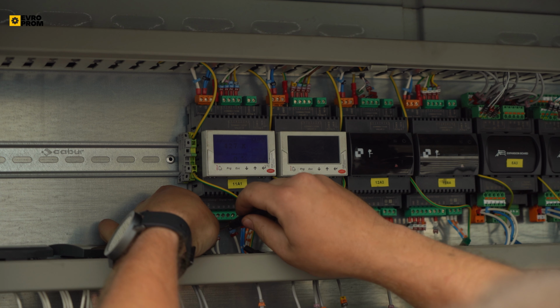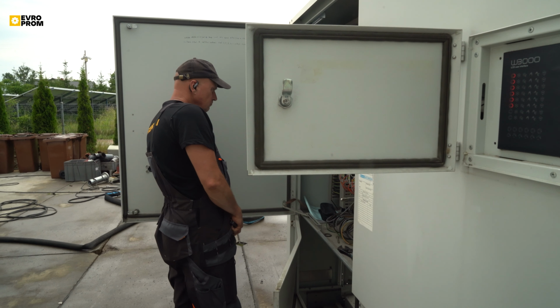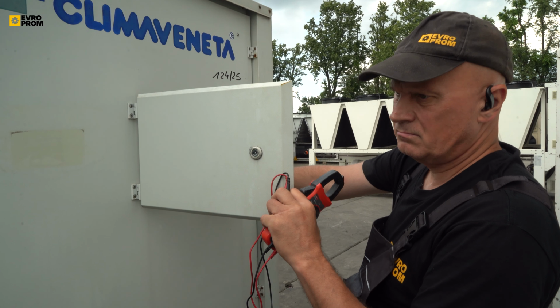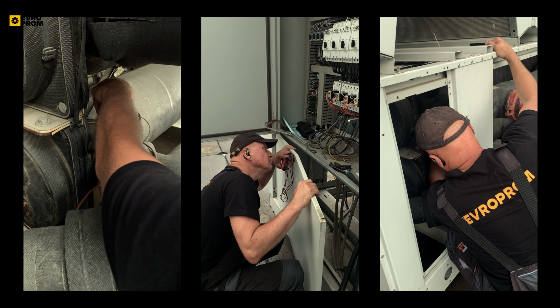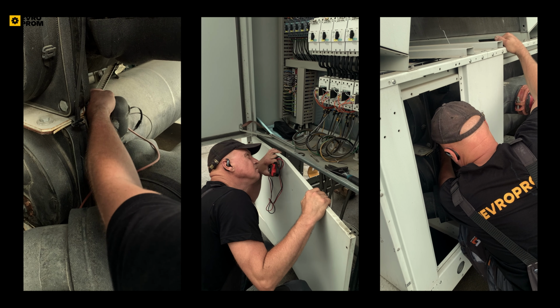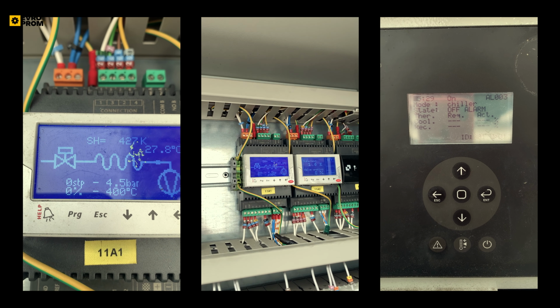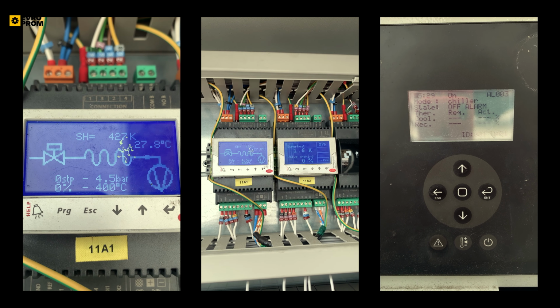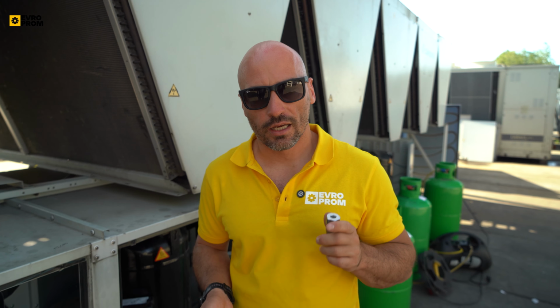But the diagnostic told a completely different story. After checking the sensors and signal wiring, we discovered the problem was much smaller: the damage was in a suction pressure sensor. The controller was getting incorrect data, so it looked like overheating, and that's why the expansion valve didn't want to open. That was the real problem.